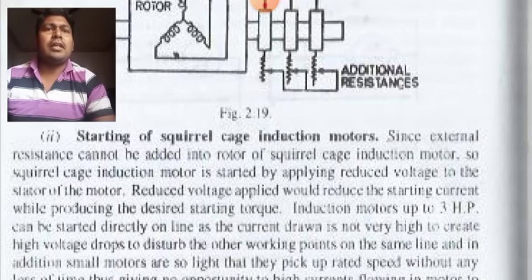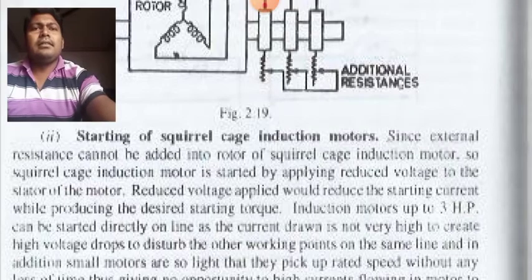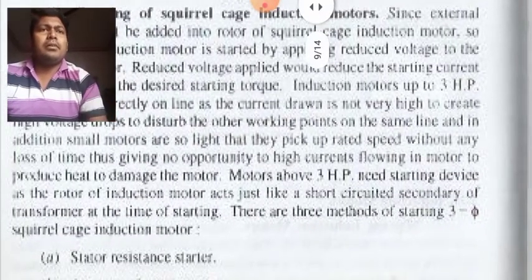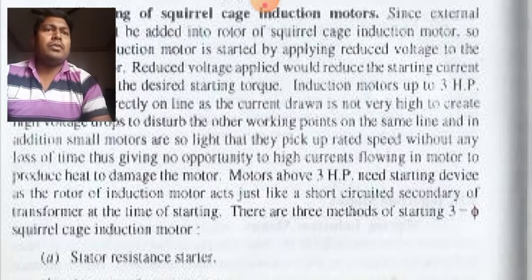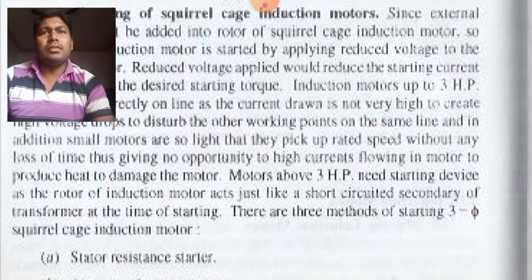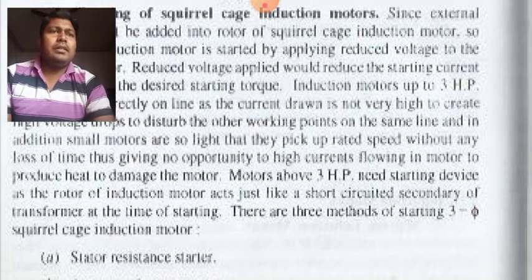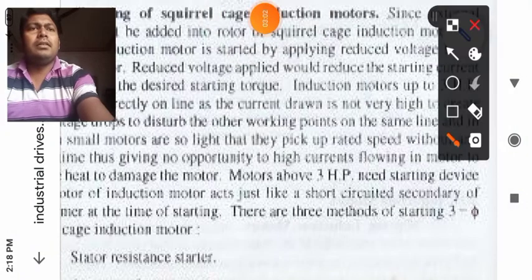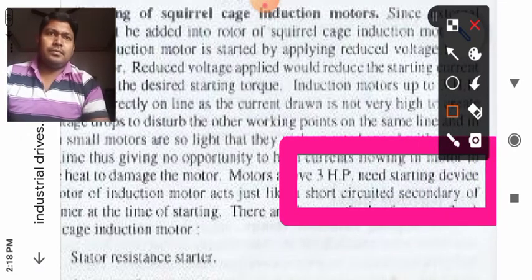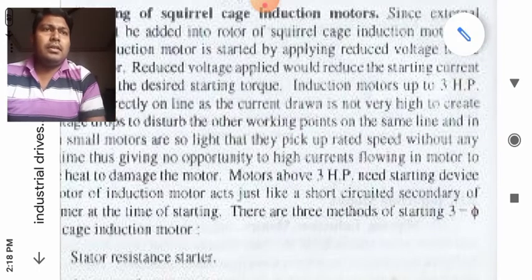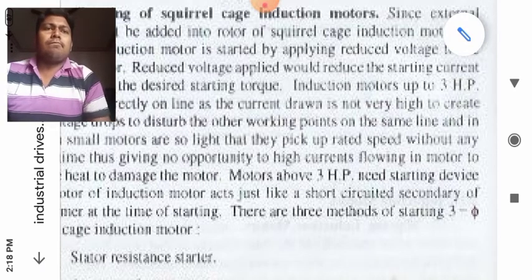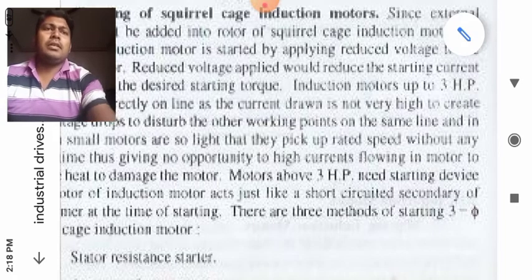Induction motors up to 3 HP can be started directly online, as the current drawn is not very high to create a high voltage drop that would disturb the other working points on the same line. In addition, small motors are so light that they pick up rated speed without any loss of time, so there is no opportunity for high currents flowing in the motor to produce heat and damage the motor. So motors above 3 HP need starting devices. You should remember, students, any motor having a capacity above 3 HP needs a starting device. Why does it need a starting device? So as to protect its winding. Otherwise a heavy amount of current will be drawn, resulting in damage of the motor. So a motor above 3 HP should be used with a proper starter.